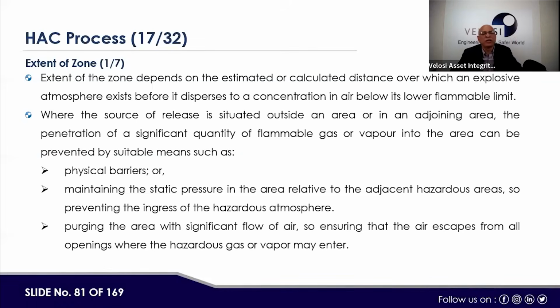Normally, we have seen in the diagrams a full area, then up to 1.5 meters, up to 3 meters, up to 15 meters. So those are the extents. Now, the extent of a zone depends on the estimated or calculated distance over which an explosive mixture exists before it disperses to a concentration in air below its lower flammable limit, where the source of release is situated outside an area or in an adjoining area, the penetration of a significant quantity of flammable gas or vapor.